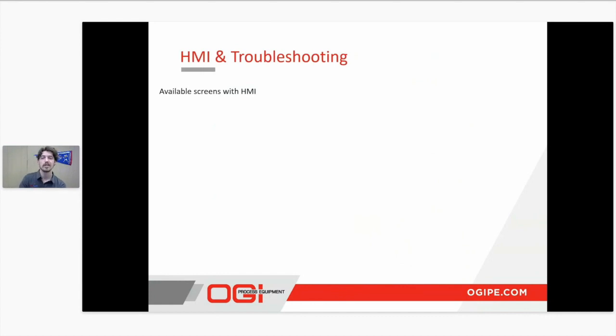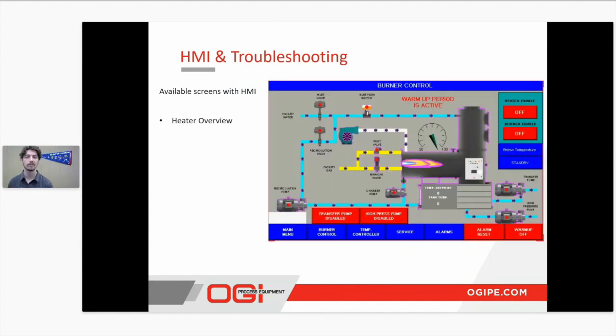Next, a little bit about the HMI and troubleshooting. Specifically with these units for our rentals, we're going to have it equipped with an Automation Direct HMI. That HMI comes standard with an internet connection. So you can actually remote monitor any alarms from your system, what water temperature you're pumping out at. Essentially, if there's anything wrong with it, you can see it via the internet on that connection.